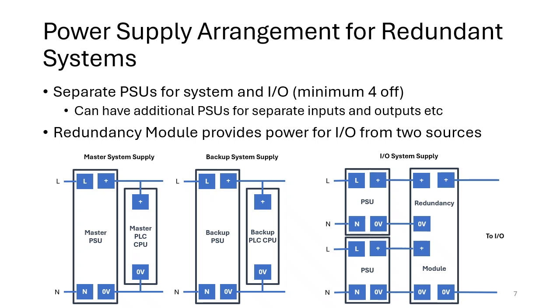So you'd have your master system supply, so a master power supply which controls the master PLC, and then you'd have a backup system supply and the backup power supply controlling the backup PLC. And in the case of any single point of failure, there you're covered, because the other system will take over if the first one fails. For the I/O system though, the I/O system is often not redundant. You're often using a Simplex I/O solution, but you still want a redundant power supply.